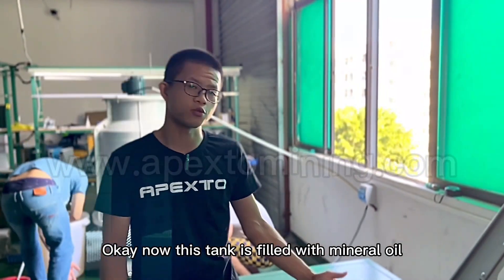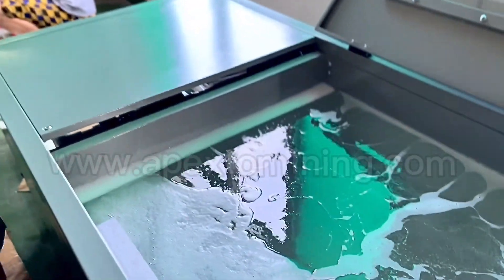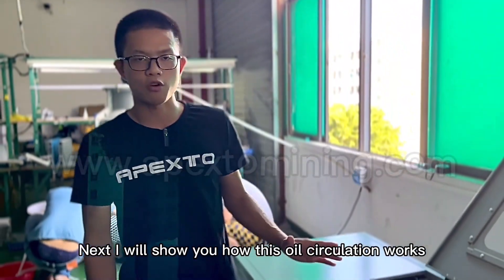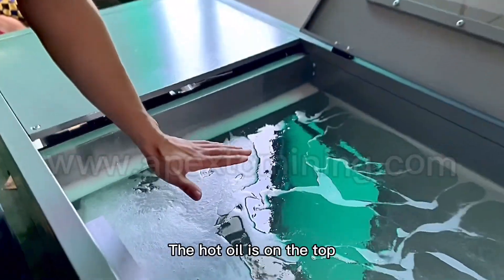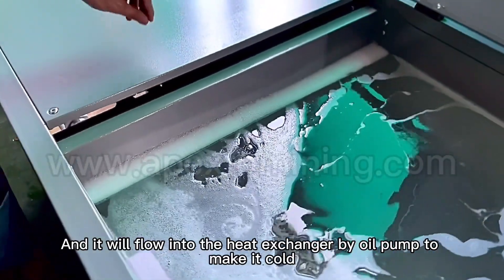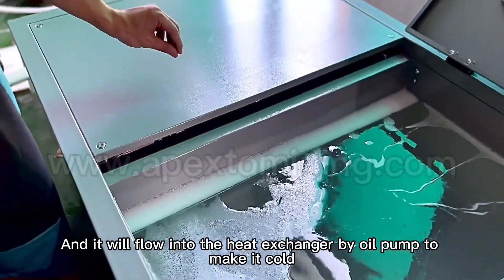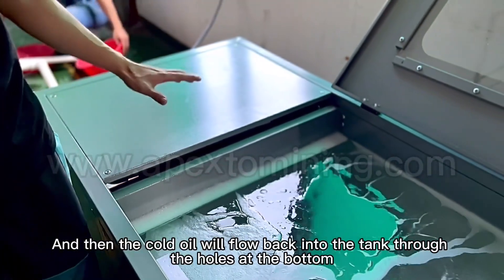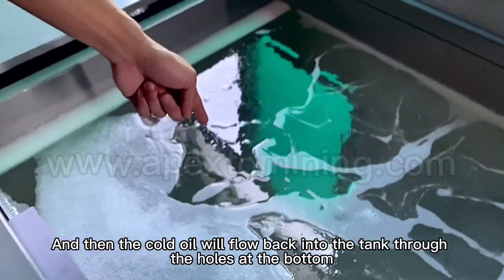Next, I will show you how this oil circulation works. The hot oil is on the top and it will flow into the heat exchanger by the oil pump to make it cold. Then the cold oil will flow back into the tank through the holes at the bottom.